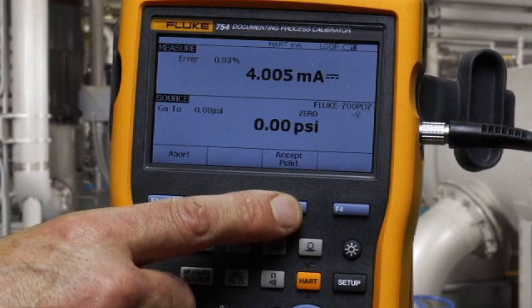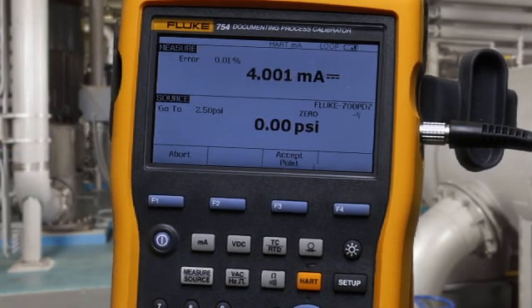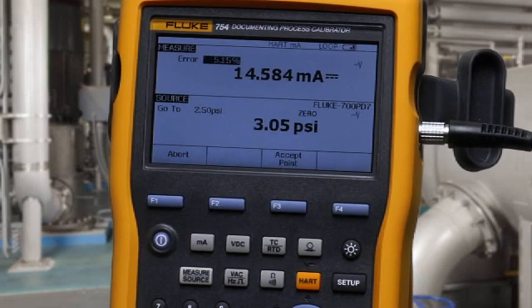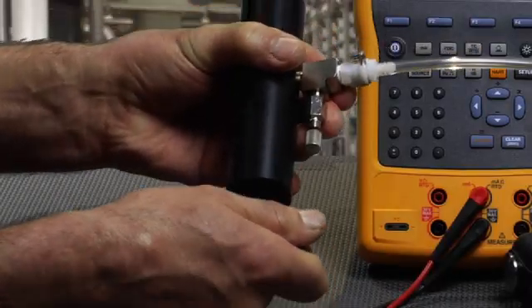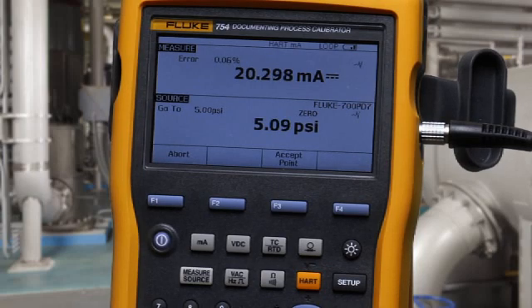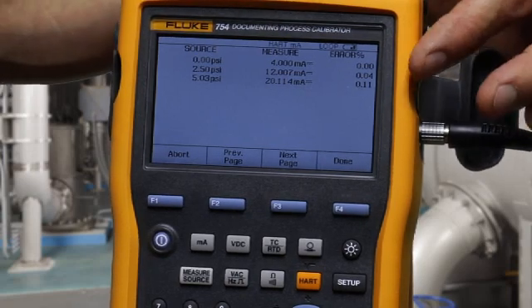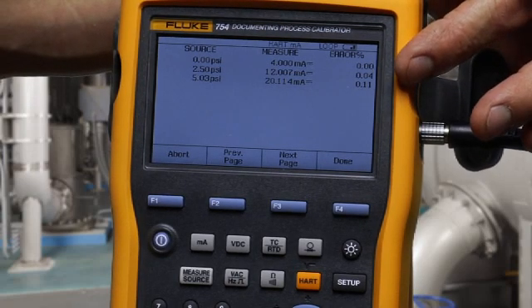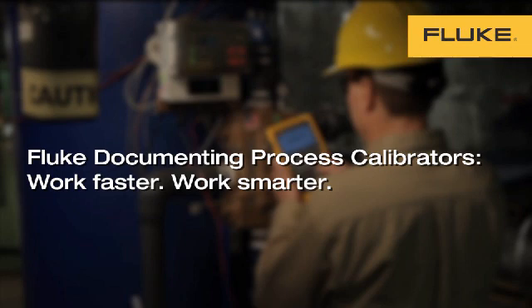Apply the zero percent value, then 50%, and then 100% at 5 PSI. The test is complete. You can see the applied pressure and measured milliamp. In this case, all the errors are less than 0.25% and the test passes. That is how you calibrate a Rosemount 3051 HART Smart Pressure Transmitter using the Fluke 754 Documenting HART Process Calibrator. Thank you.